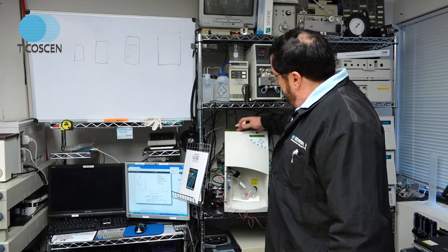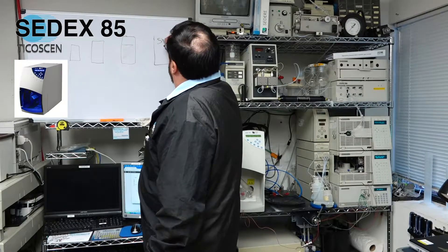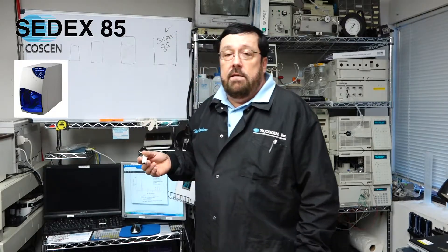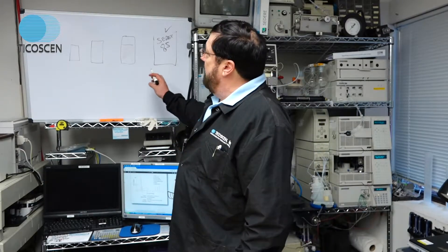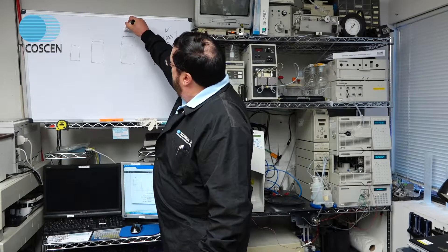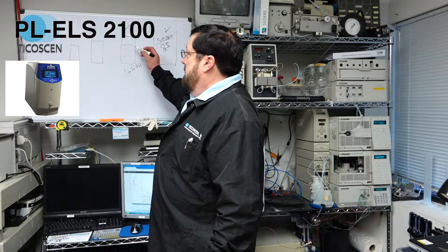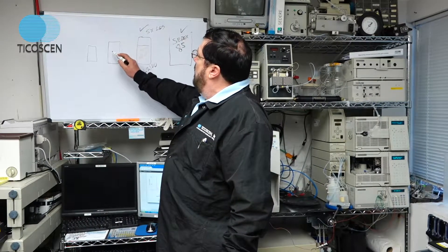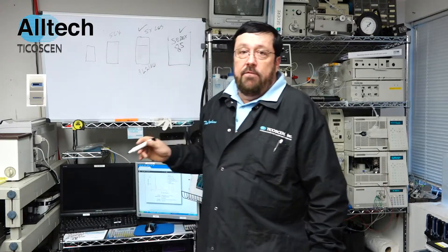The SEDEX 85, like we have right here, is very sensitive — I mean 5 ppm glucose. This SEDEX 85 is really the gold standard for sensitivity; 5 ppm glucose injections easily achieve a 1000-to-1 signal-to-noise ratio. If you run a 5 ppm glucose standard on the Polymer Labs 2100 — now the Agilent ELSD, since Agilent owns the Polymer Labs variant — it's about five times less responsive. On the Alltech 2000 style ELSD it's about 50 times less sensitive at 5 ppm glucose.